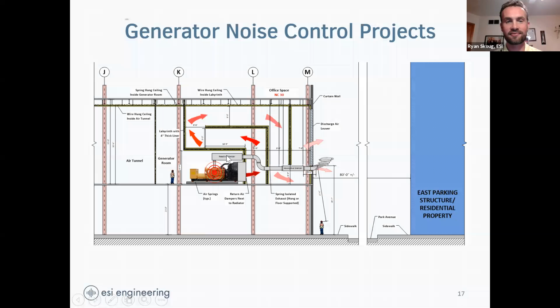So we got these crazy reactive silencers with chambers inside. But the way generator engineering works for sound, you can't use more than one reactive silencer, otherwise they start talking to each other and you get resonances, where your sound level at some tone can actually be worse with 2 silencers than with just 1.